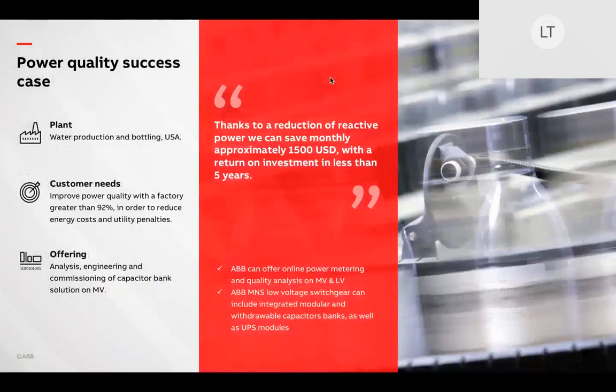This next slide shows an example of where power quality was an issue. The customer, a water production and bottling company located in the United States, had an issue where the power factor was in the low 80s. And of course, as you know, the optimum goal is to get one, which is unity. And they were paying a penalty charge to the power supplier based on every percentage below unity.